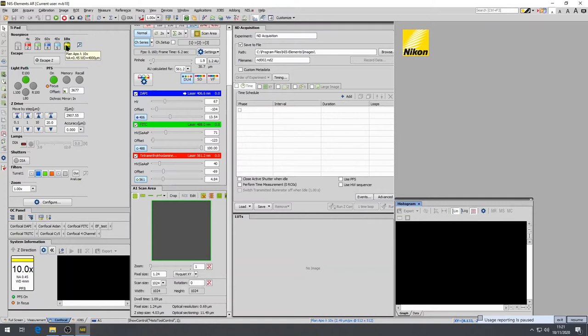Regarding oil, do not put too much onto the objective. A small drop is sufficient. If too much oil is used, it can enter into the objective and render it useless.